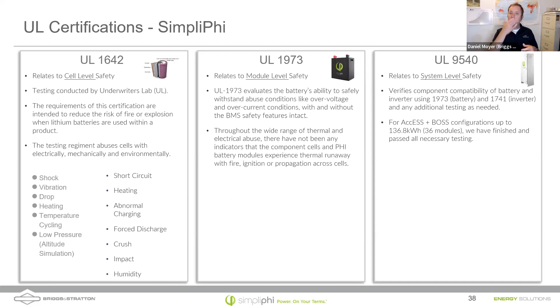Further, we use UL 9540A, which is a large-scale fire testing that a lot of jurisdictions and utilities are now requiring for interconnection agreements. It's not a certification, just a test method. I won't read all of this, but essentially they force a cell into thermal runaway and watch what happens.